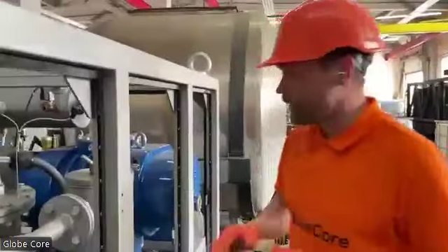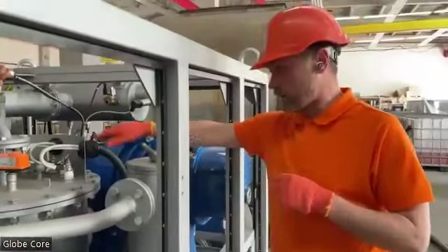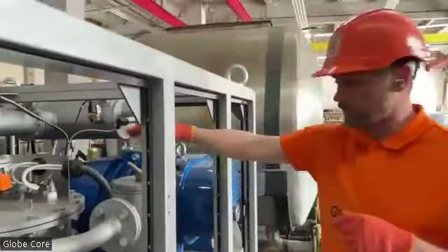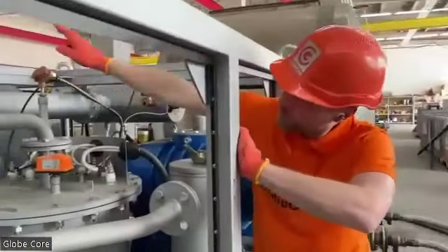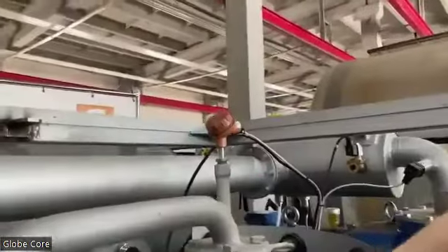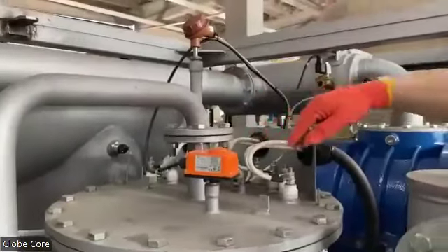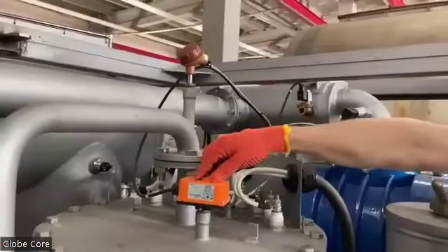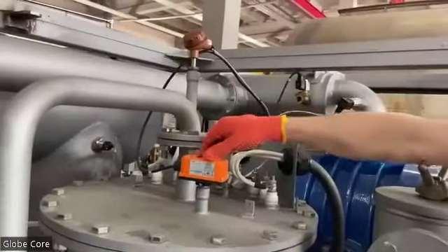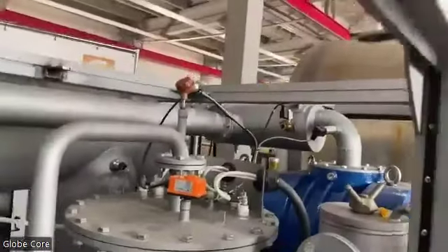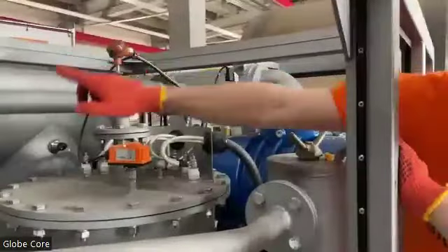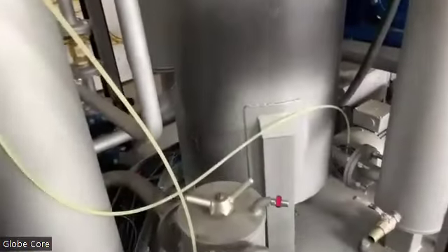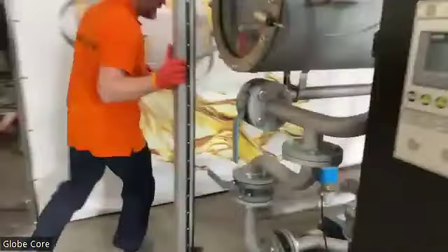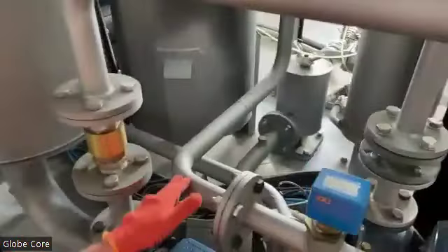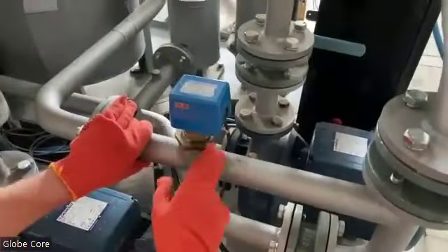So each section has a capacity of from 50 to 60 kilowatts. So 3 separately controlled sections of the heater. Altogether, it makes 150 to 180 kilowatts. Then what we can see, there is the temperature sensor and the thermostat. So normally it has a setting like 80 to 90 centigrade. So oil after the heater goes in this line. Let me show you. It comes here from the heater. It comes here, and here we have the flow sensor.